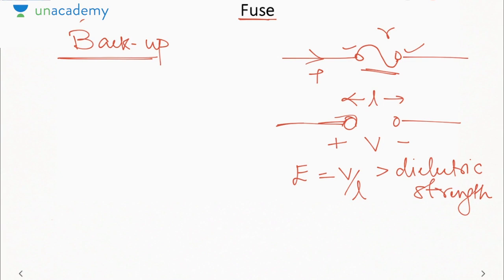Now why is the fuse used as a backup protection, not as a primary? The thing is, primary protection operates first. If the fuse operates first, then it will get damaged. You will have to replace it. So it is better that you use something else for primary protection, and if that does not work, then your last resort should be the fuse. If nothing works, then the fuse must melt down to disconnect the faulty part. But if other things can work properly, then there is no need to melt the fuse. That is why it is always used as a backup protection.